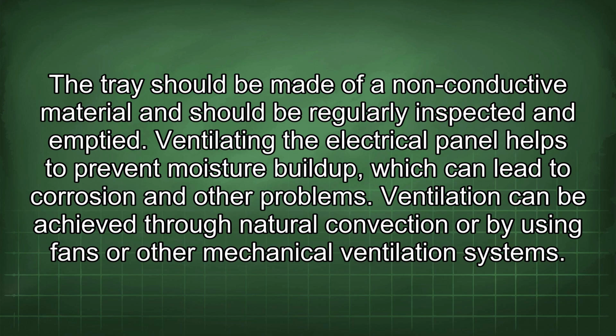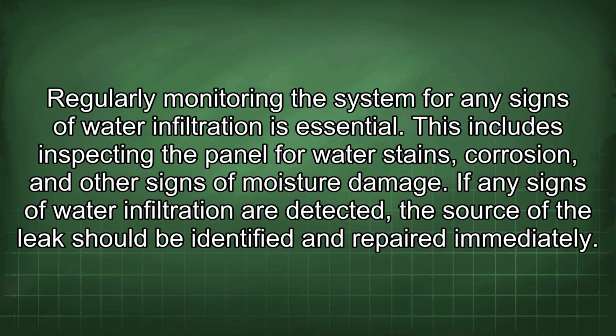Ventilating the electrical panel helps to prevent moisture buildup, which can lead to corrosion and other problems. Ventilation can be achieved through natural convection or by using fans or other mechanical ventilation systems. Regularly monitoring the system for any signs of water infiltration is essential. This includes inspecting the panel for water stains, corrosion, and other signs of moisture damage. If any signs of water infiltration are detected, the source of the leak should be identified and repaired immediately.